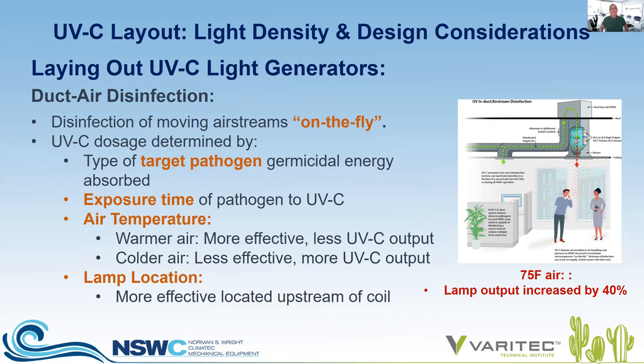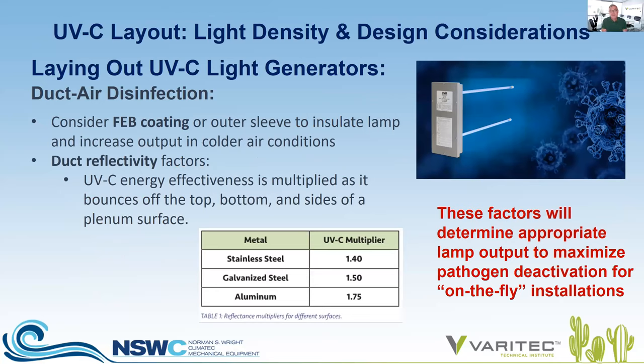Some other duct air disinfection considerations: do you want to use FEP coating or outer sleeve to insulate the lamp and increase output in colder air conditions? Another factor is duct reflectivity — stainless steel, galvanized steel, and aluminum reflect UVC light at different intensities. If you select a dosage, we'd want to know what type of casing surrounds the device so we can add an extra 40 to 50 percent to the overall output due to the reflectivity factor, making it more effective than its assigned lamp output.